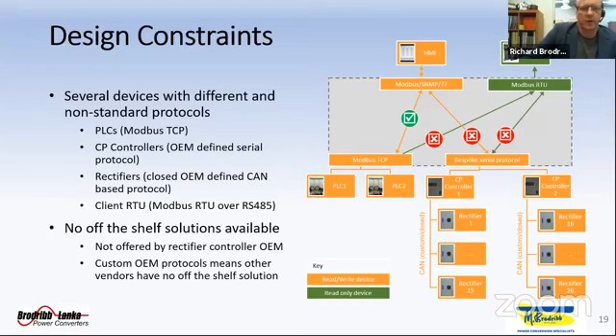With that in mind, we had a number of design constraints. We had several devices with different and non-standard protocols. We had a number of different Modbus protocols and a bespoke serial protocol that was particular to the CP controller produced by that OEM. What this meant was we had no off-the-shelf solutions available to tie everything together. So our approach was to take a modular approach where we would have at the center of it a variable database that allowed different protocols to update and pull data from the database.